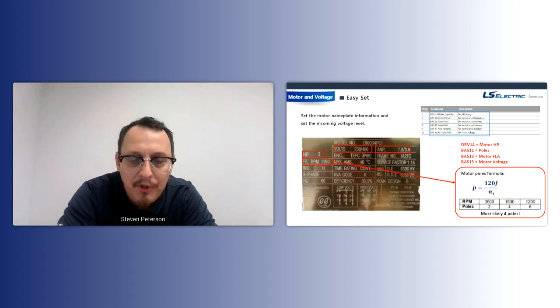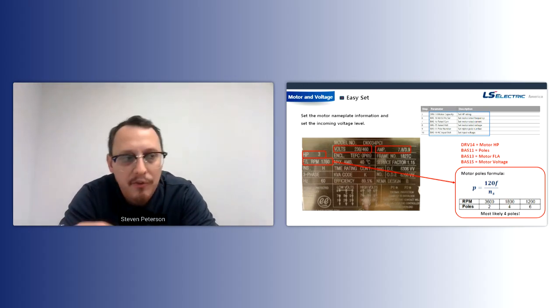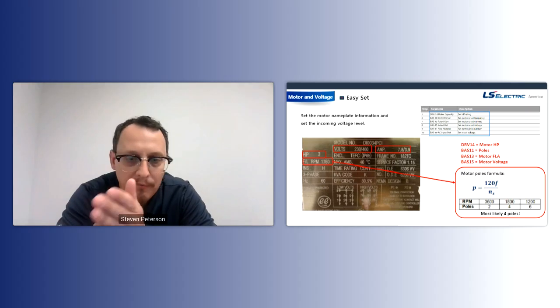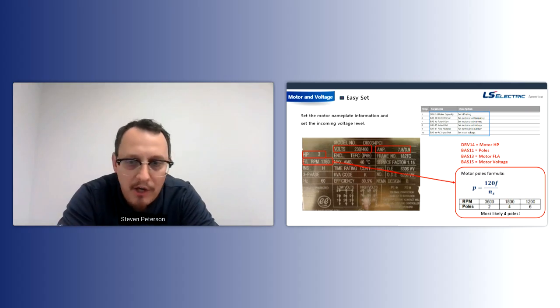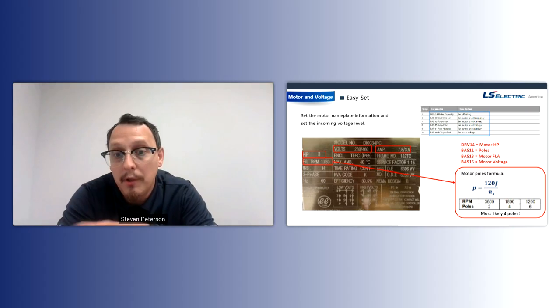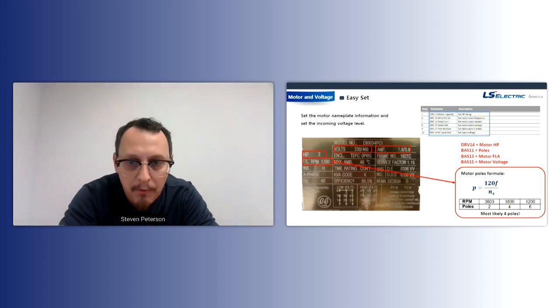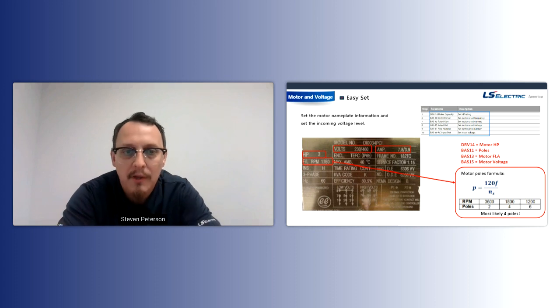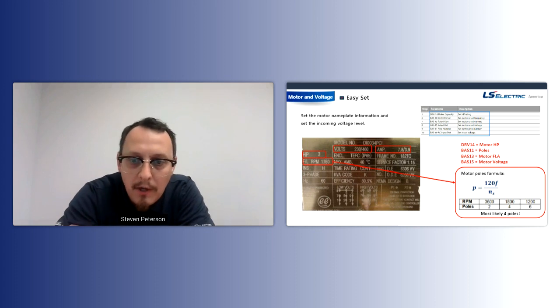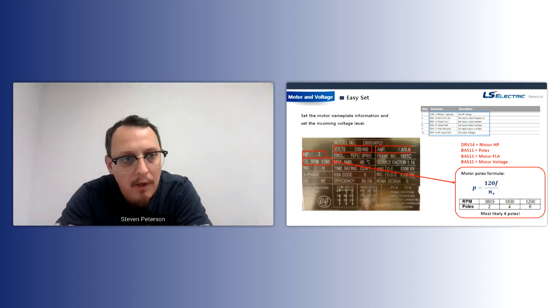And a lot of times people say, oh, number of motor poles, and they think 3 because they're thinking 3-phase, and they go to set this, but it jumps from 2 to 4. We're not actually talking about motor phasing here. We're actually talking about electromagnetic motor poles. So if you have north-south, it's always going to be in pairs. So you're going to have 2, 4, 6. And I think most people, guys, are going to run in either 2-pole or 4-pole. A lot of submersible pumps are 2-pole, and that's because they're like 3,500 RPMs. And then like centrifugal pumps and items like maybe vertical turbines and stuff, those are typically 4-pole.